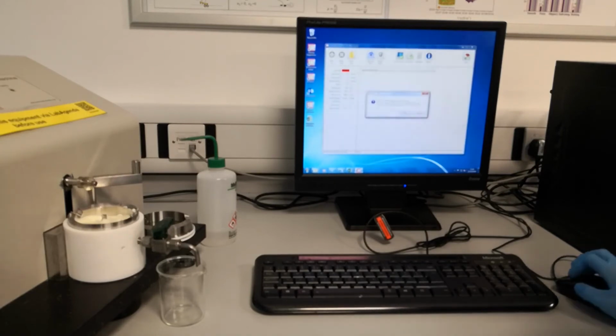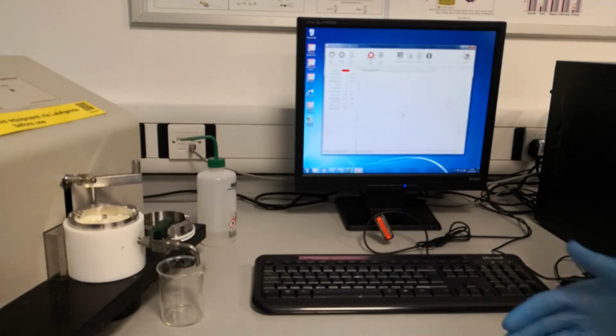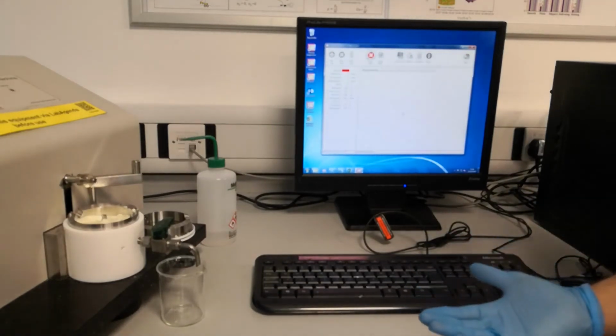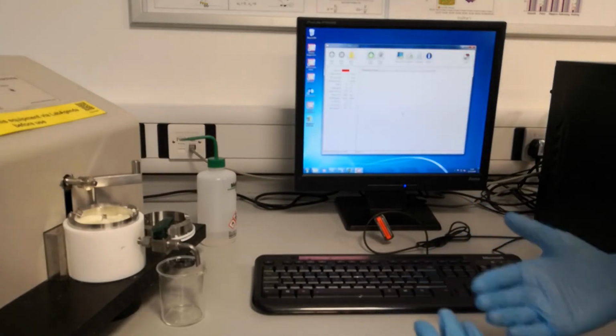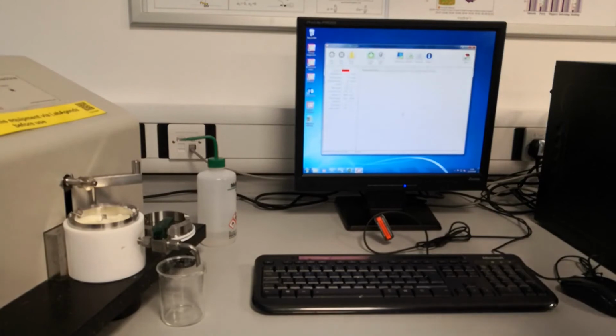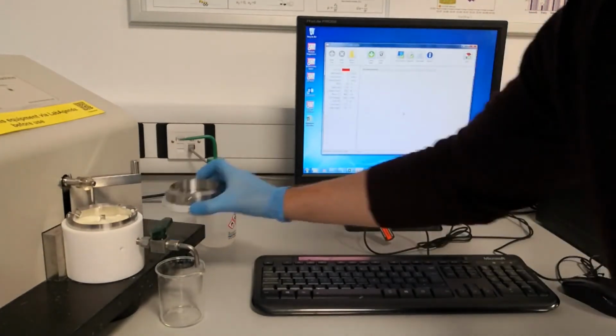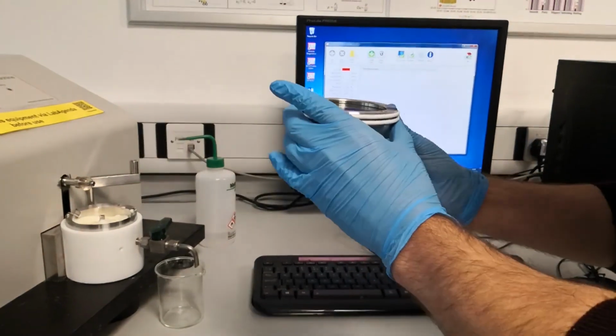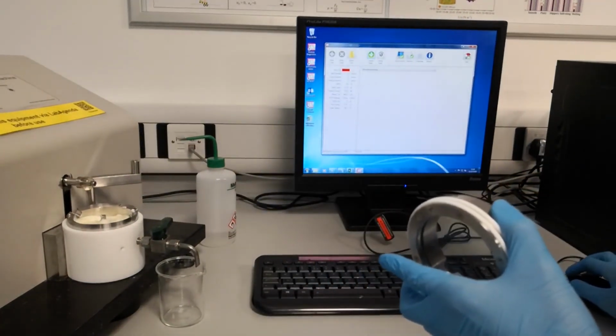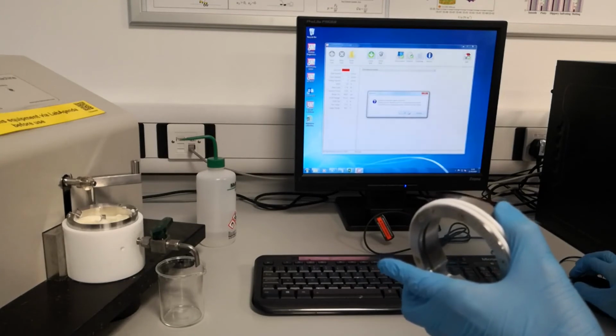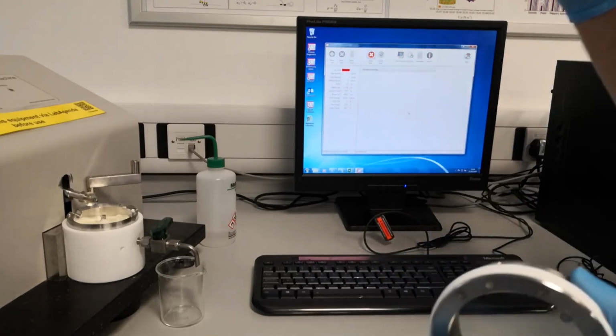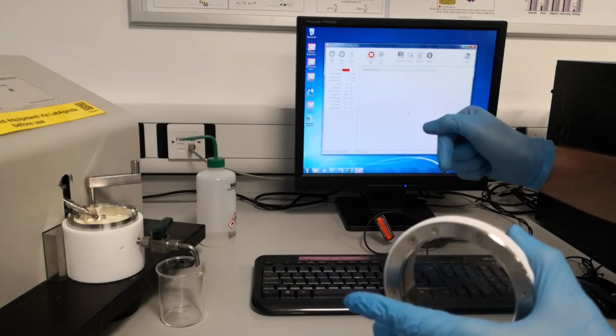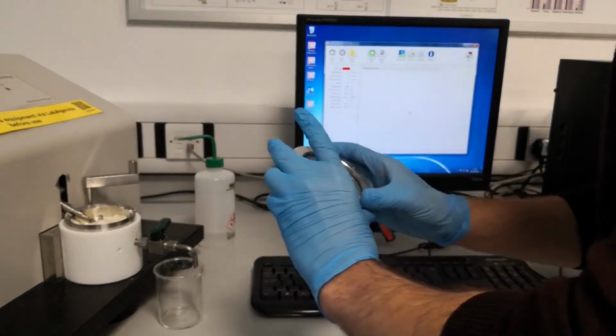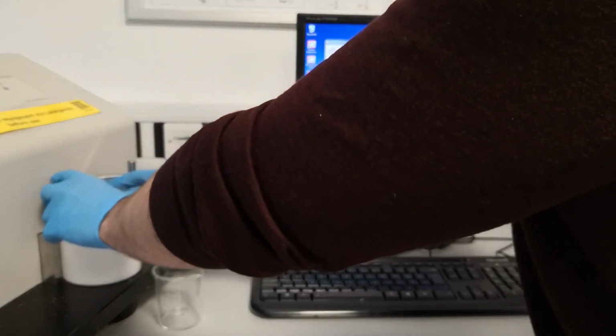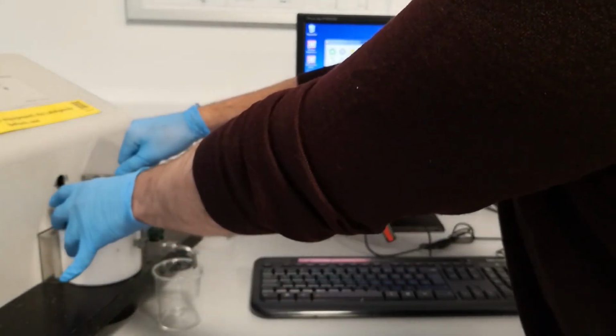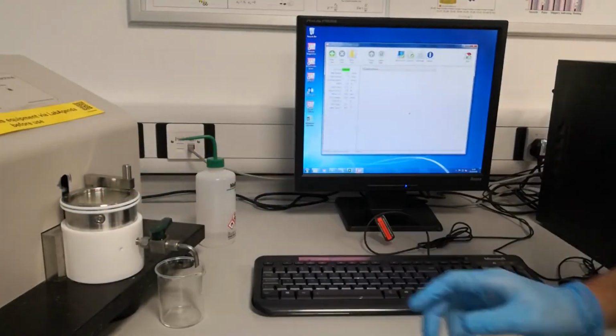The first thing you need to do is initialize the bowl. Basically, if the bowl is loaded against the disc or in another condition, it initializes and goes to the initial condition. Then you would have the lid, and you lower the bowl. The bowl would move into contact with the disc. You would mount the lid and secure it with this lever.